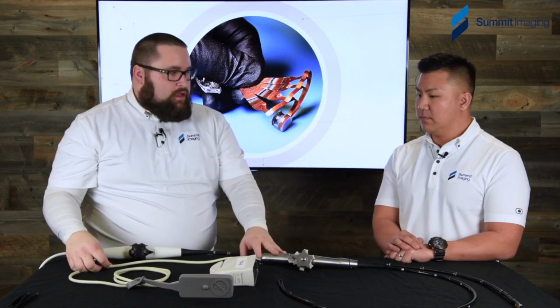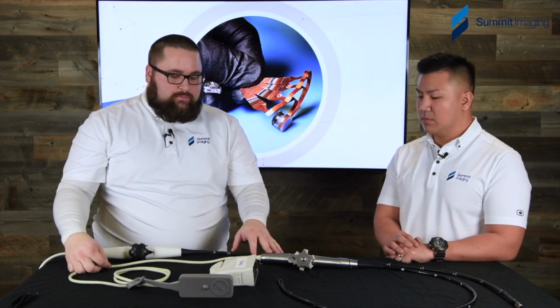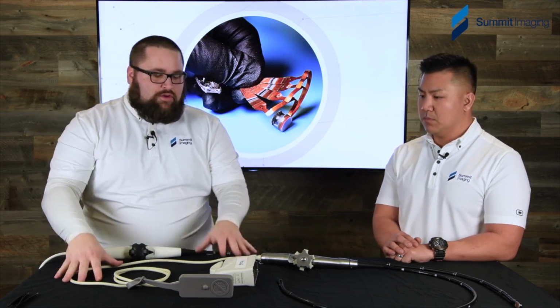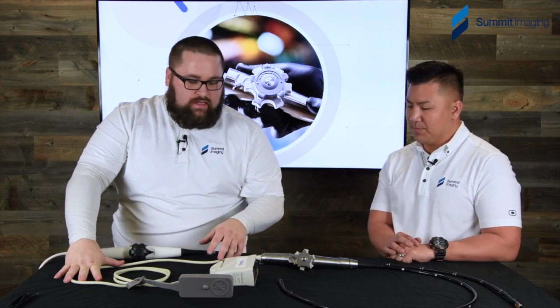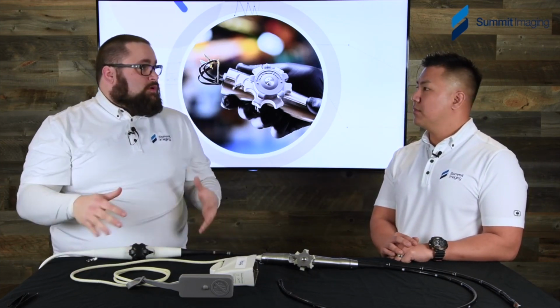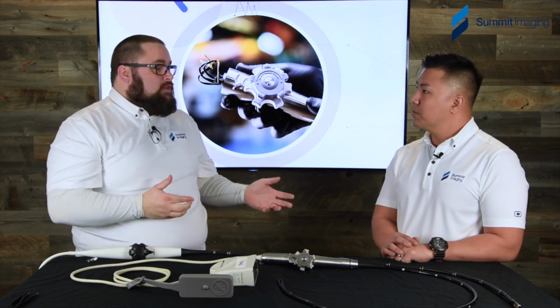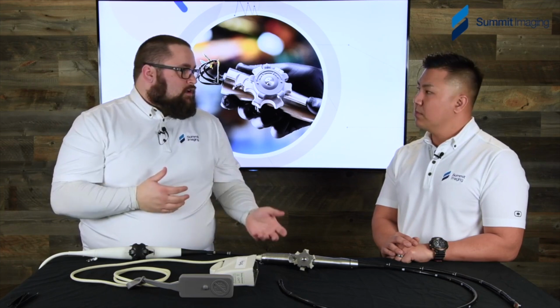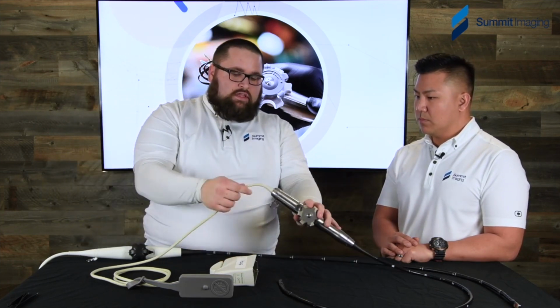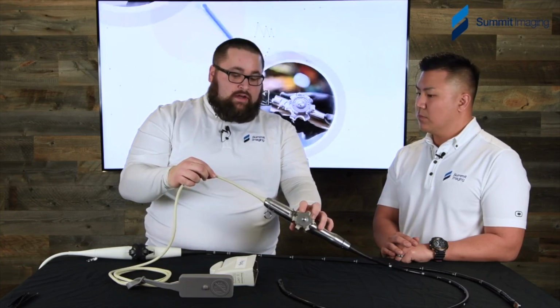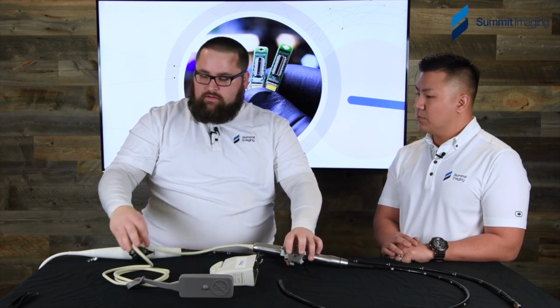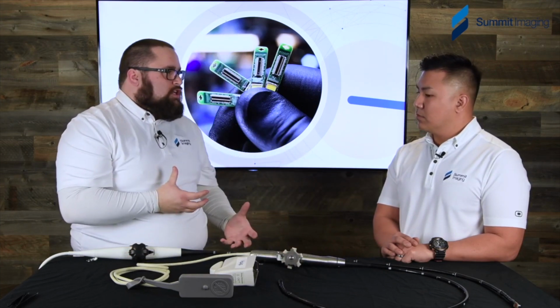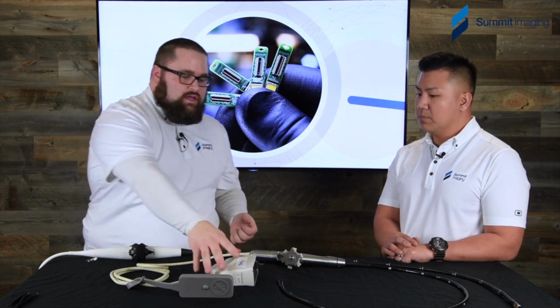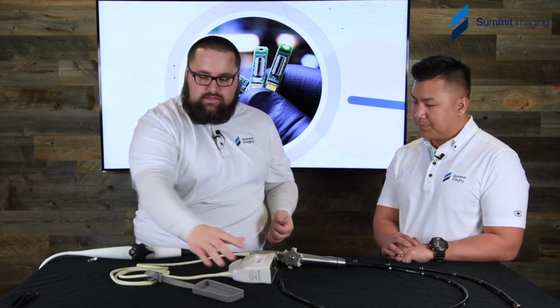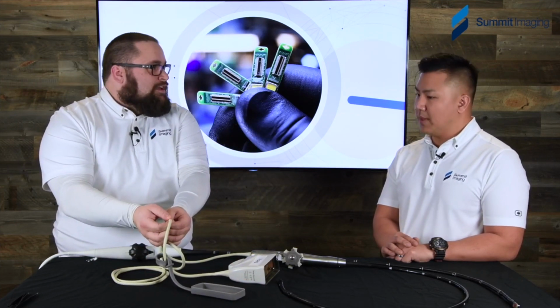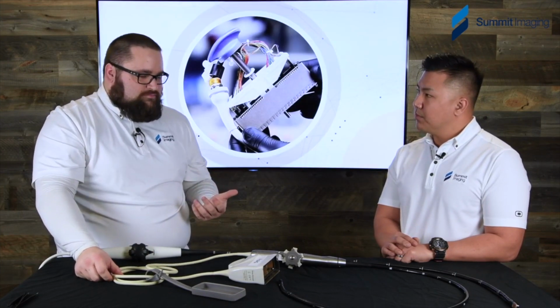Absolutely. All right. So as we start looking at the rest of the transducer, things start to get a little standard. You still have cords and connectors on your C52, C51s, everything else you see across. But it's still exposed to a way harsher environment. You can have the problem with getting rolled over by carts. It's traveling down hallways. It's in totes. So the strain reliefs on these T-probes are something that you want to look after and give some actual care to. Inspect regularly. We get a lot of pinched cables just from being shut in a machine door, a lot of the sterilizers, because you want to keep this can out of the sterilizer. It means a pinch will start to form kind of in the same spot on the cable every time. And then we see a lot of damage just from the transportation.